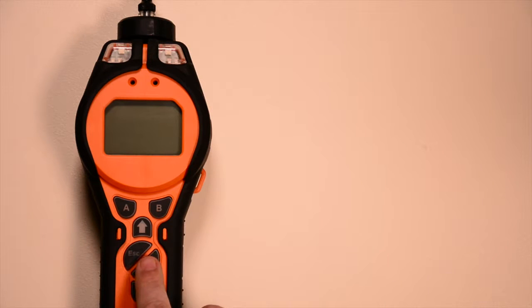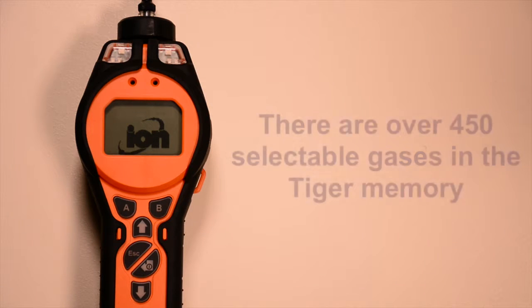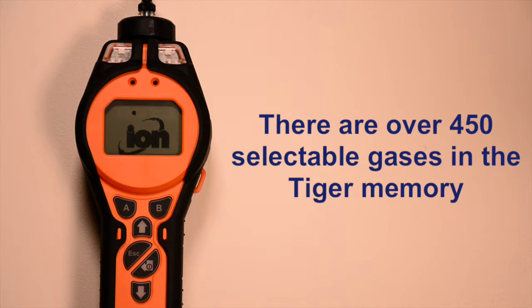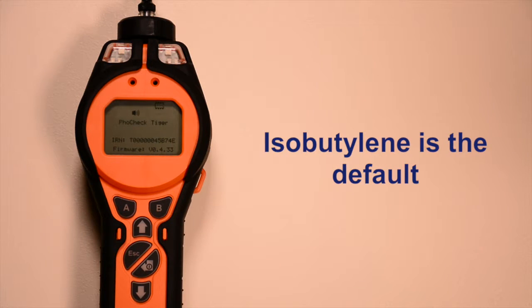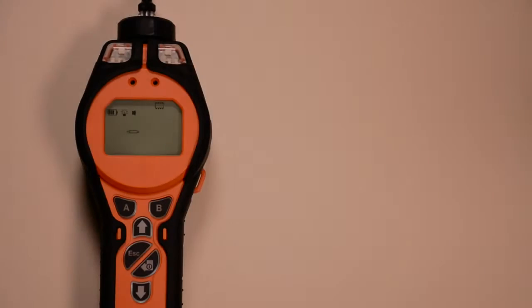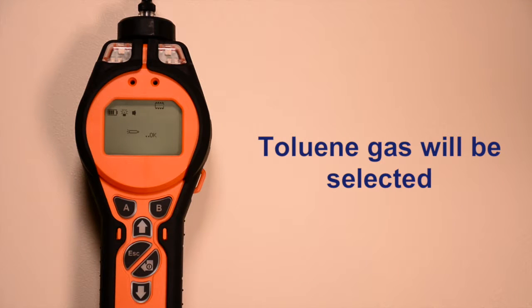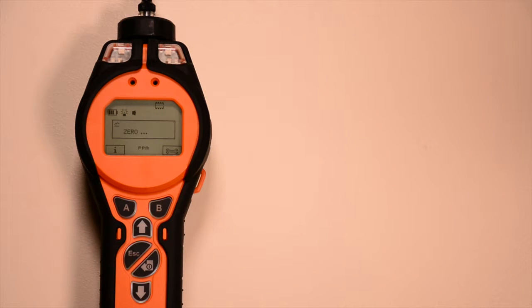Switch on your Tiger instrument and wait until a reading is displayed. There are over 450 selectable gases held within the Tiger memory, but isobutylene is the default. In this example, toluene gas will be selected.